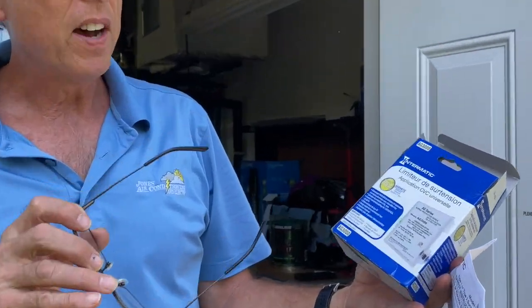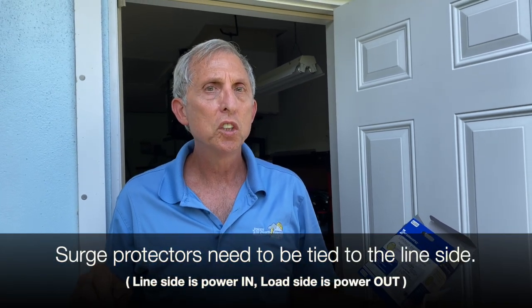I have an Intermatic surge protector here — it's one of the better ones on the market. A lot of times we get them rated up to 200 amps and they have to be tied to the line side of your source. Line side is power coming in; load side is power going out. This unit has three wires: one to the line side, one to the neutral, and one to the ground.